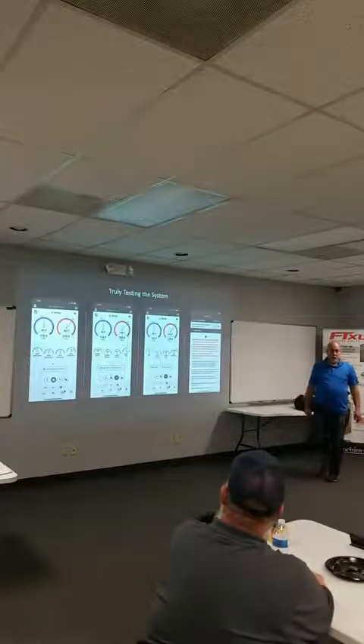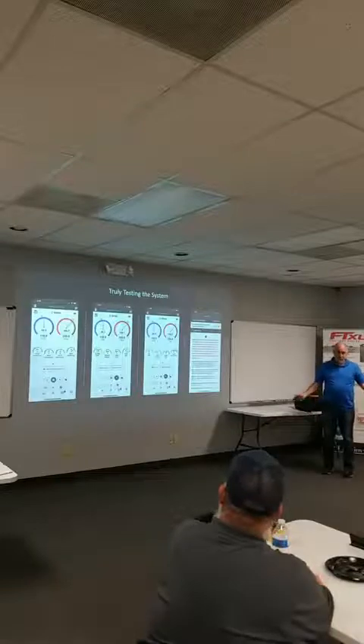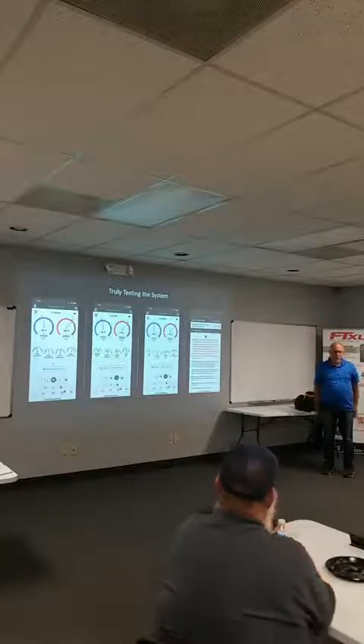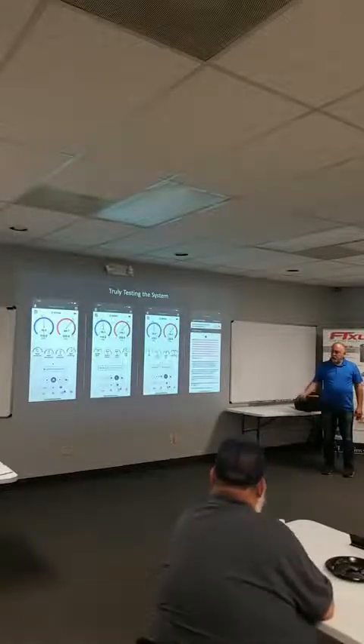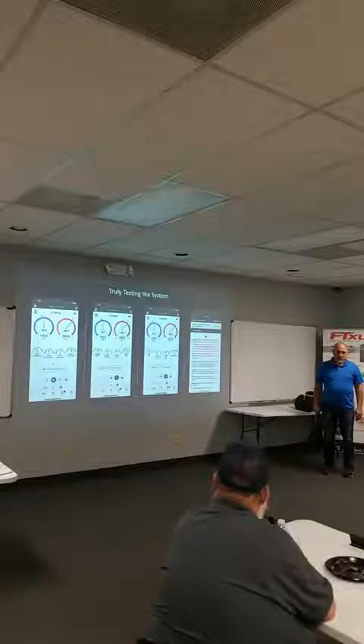Right, the unit's running fine, but the system sucks. This is why we gotta take a systems approach and not an equipment approach, because you guys are going up and you're checking equipment, equipment's perfect. But your customer's losing a third of their cooling because of duct leakage, right? They're losing a third of their cooling because the economizer's leaking.